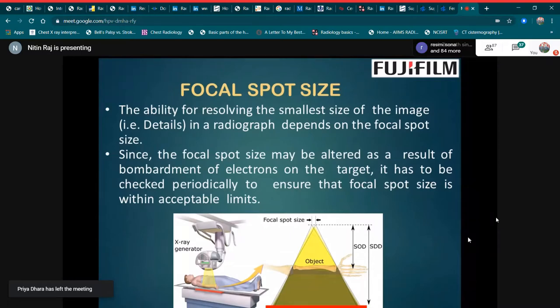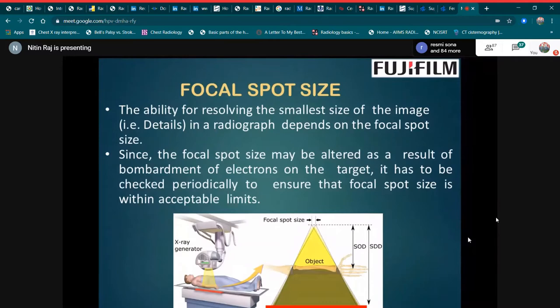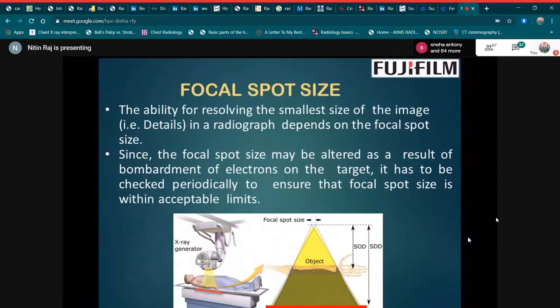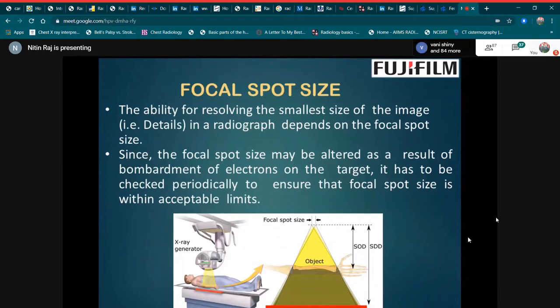Regarding focal spot size, the ability to resolve the smallest details in a radiograph depends on the focal spot size. Since the focal spot size may be altered as a result of electron bombardment on the target, it has to be checked periodically to ensure that the focal spot size is within acceptable limits.